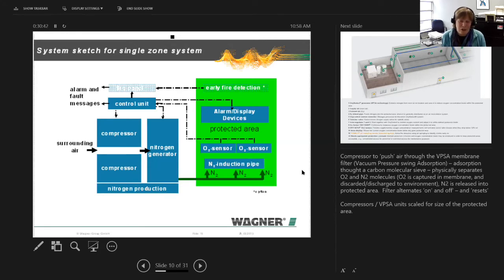The nitrogen-rich air is placed into the green box, which is the protected area, and that's just piped through. It's just a standard 4-inch pipe that comes out, and it's just open-ended into the protected area. It does pass through a check valve so that it's pushed into that environment. So you have a solenoid valve that only allows the gas flow in one direction. The protected area is managed with the oxygen sensors. That feeds back into the control unit. That control unit then either calls for more or less nitrogen.